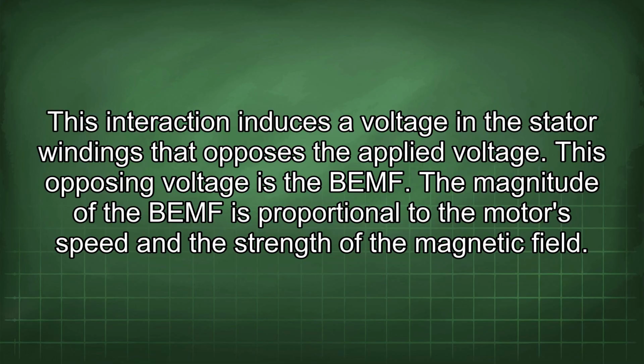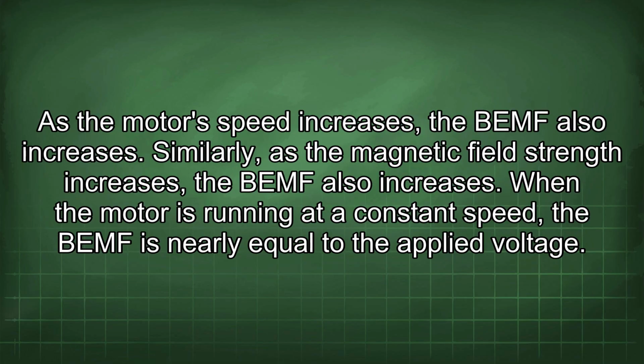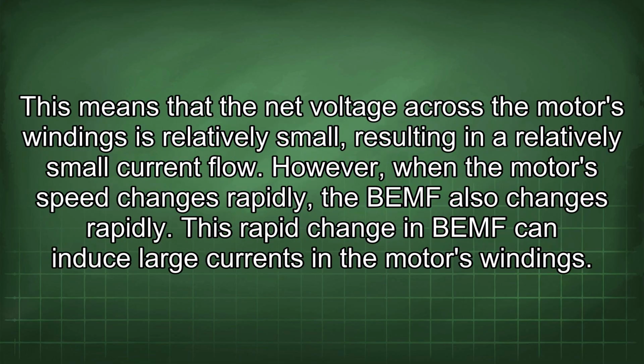The magnitude of the BEMF is proportional to the motor's speed and the strength of the magnetic field. As the motor's speed increases, the BEMF also increases. Similarly, as the magnetic field strength increases, the BEMF also increases. When the motor is running at a constant speed, the BEMF is nearly equal to the applied voltage. This means that the net voltage across the motor's windings is relatively small, resulting in a relatively small current flow.